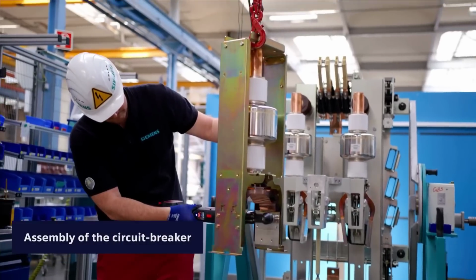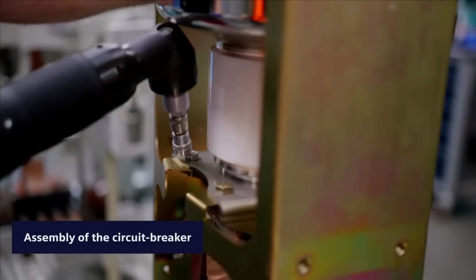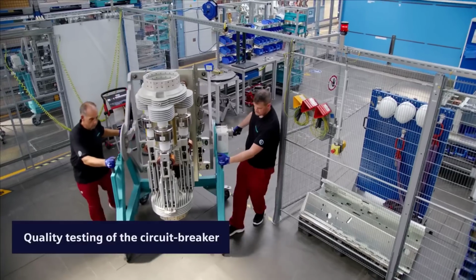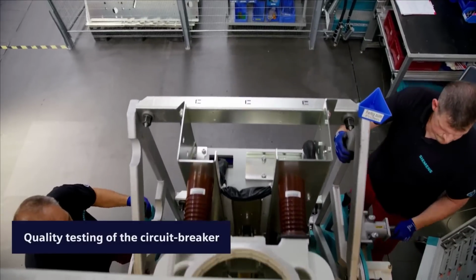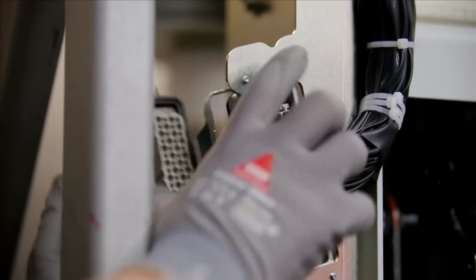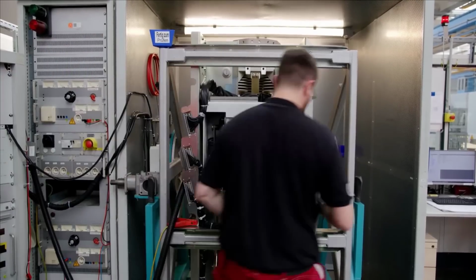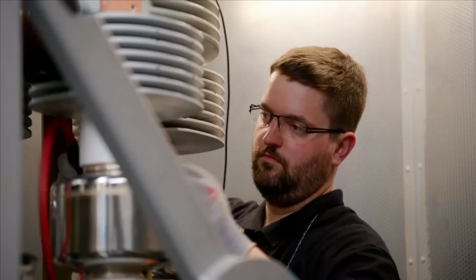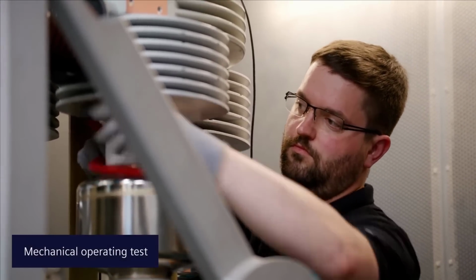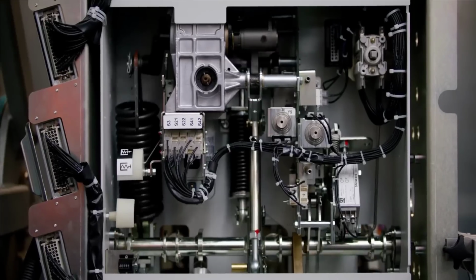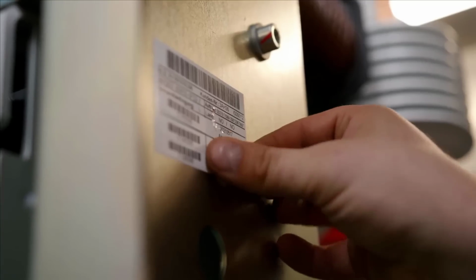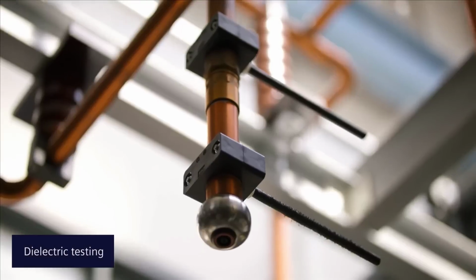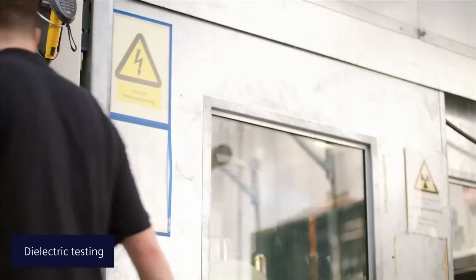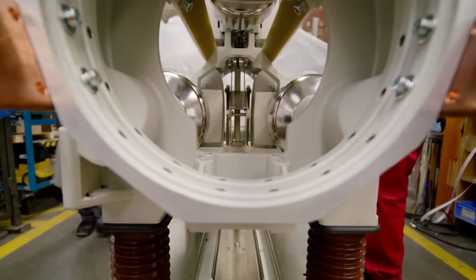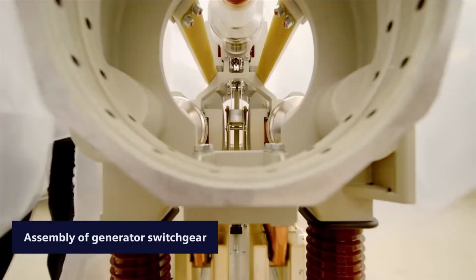Components are integrated to assemble the circuit breaker unit. The circuit breaker undergoes rigorous testing to ensure reliability and performance standards. Mechanical operating test verifies smooth operation and functionality of components. Dielectric testing verifies the circuit breaker's insulation integrity under high voltage.